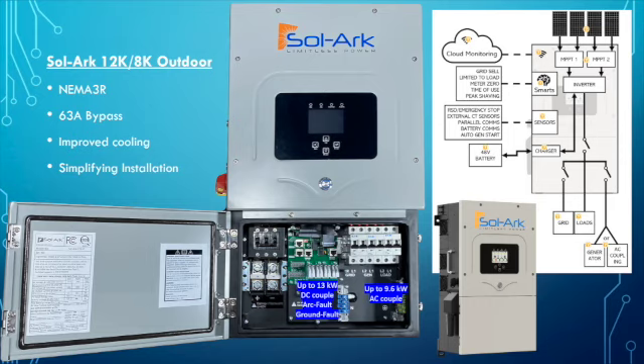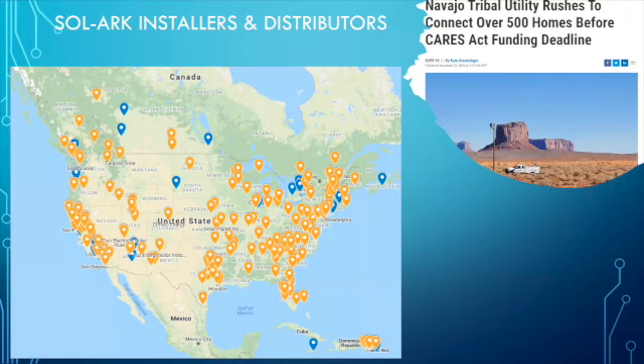Okay, so we can AC couple up to 9.6 through the generator breaker. It's a 50 amp breaker. And we can do 13 kilowatts of DC/AC coupled, with 250 amp battery breakers built in, and a 63 amp bypass.